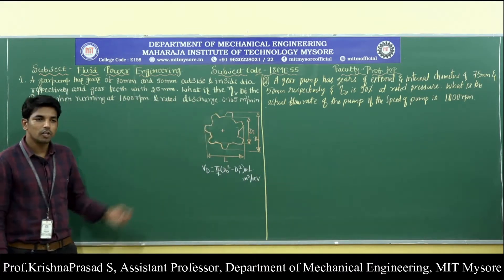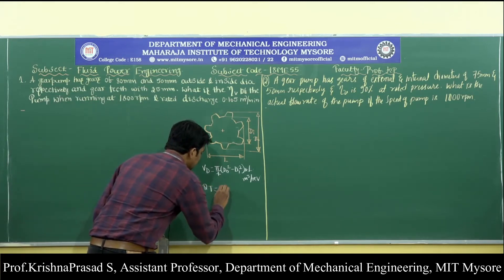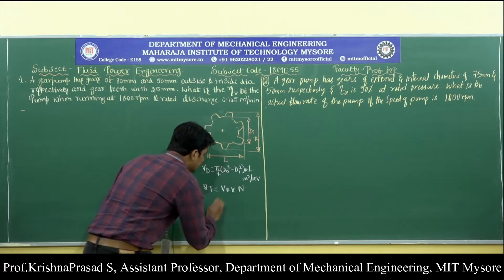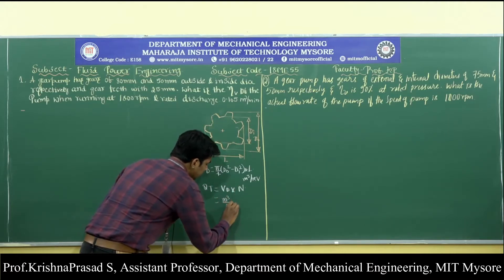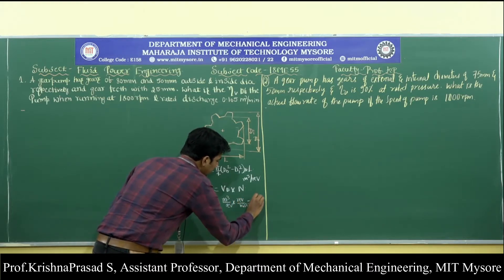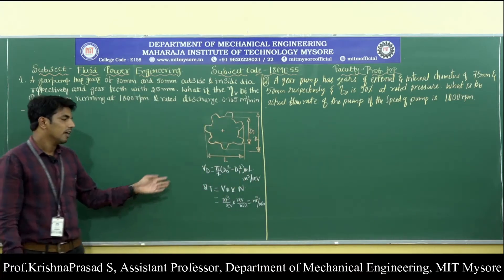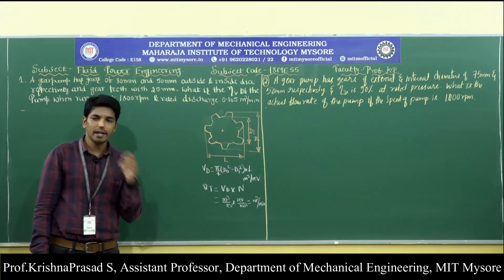The theoretical flow rate is nothing but volumetric displacement multiplied by the speed in RPM — that is, meter cube per revolution times revolution per minute — giving theoretical flow rate in meter cube per minute. This is the formula for calculating volumetric displacement as well as theoretical flow rate.